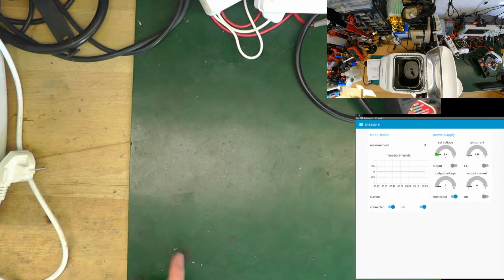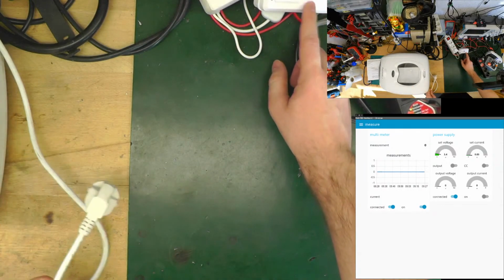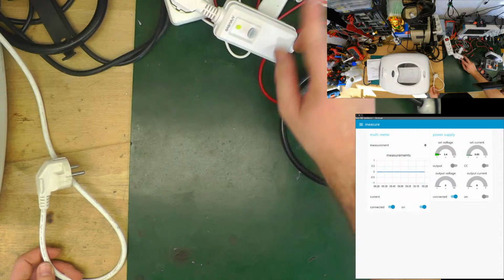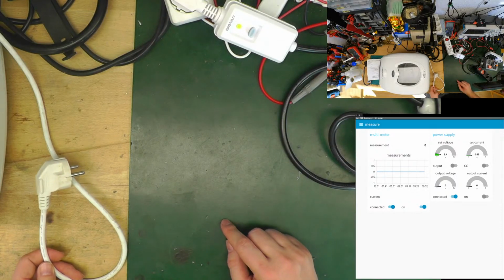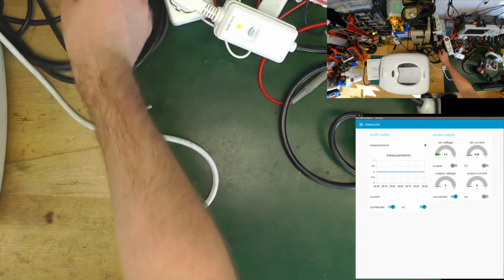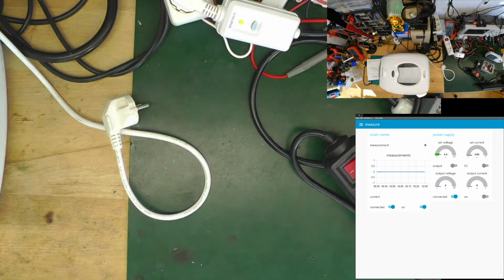But I'm surprised that it didn't blow the fuse. There's still something wrong, and I wasn't able to test it fully. I did test it once, so I know that this trips before the 30 milliamps of the main breaker. Probably it doesn't do it all the time, but with this machine it did. And the quick tester is a good thing for that.